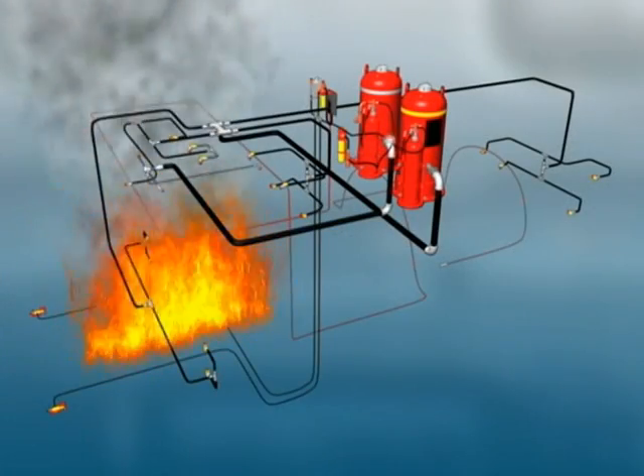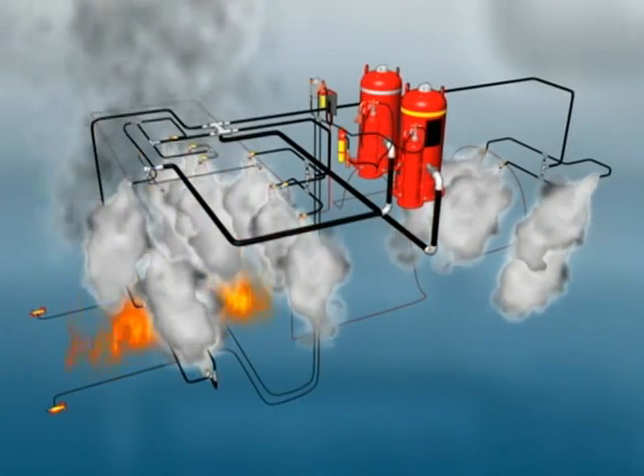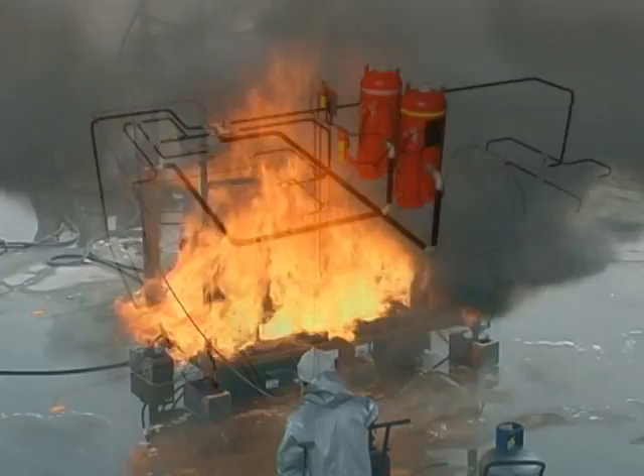When we're concerned about life safety, it takes an operator much longer to get off of a machine than it did with the very small machines of yesterday. The challenge is that we have to provide fire suppression that is going to give that operator a chance. The second phase of the system is the deployment of the LTA-101 dry chemical system to rapidly and effectively suppress the flames of a fire.